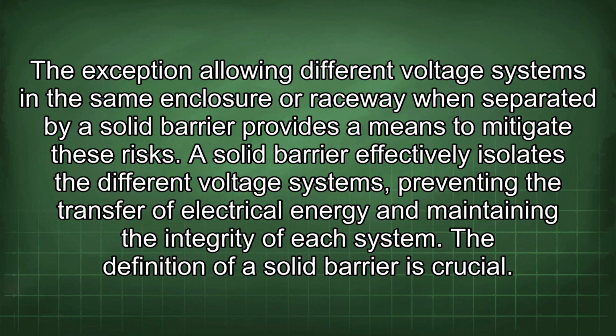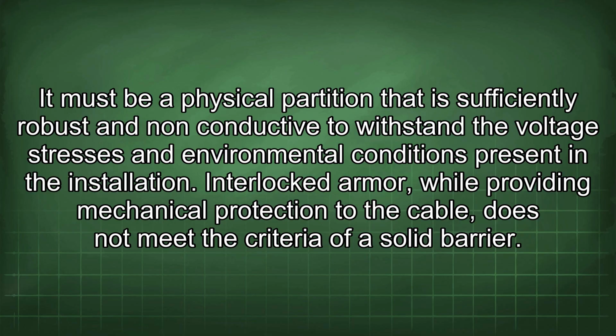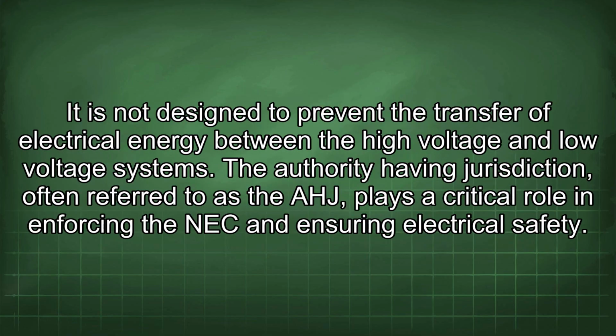The definition of a solid barrier is crucial. It must be a physical partition that is sufficiently robust and non-conductive to withstand the voltage stresses and environmental conditions present in the installation. Interlocked armor, while providing mechanical protection to the cable, does not meet the criteria of a solid barrier. It is not designed to prevent the transfer of electrical energy between the high voltage and low voltage systems.